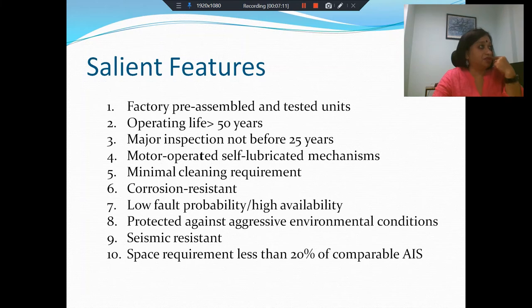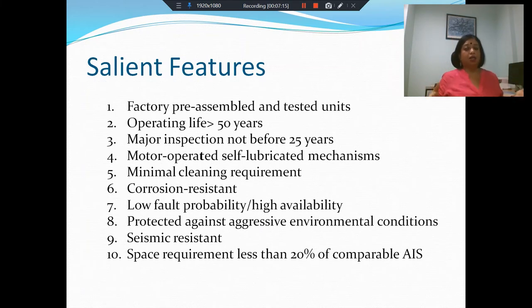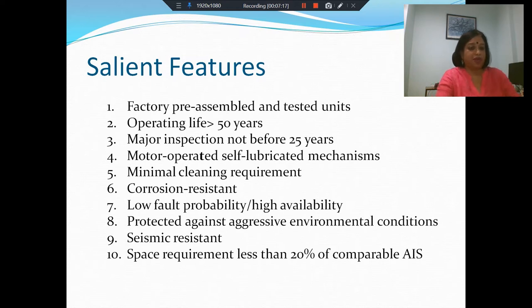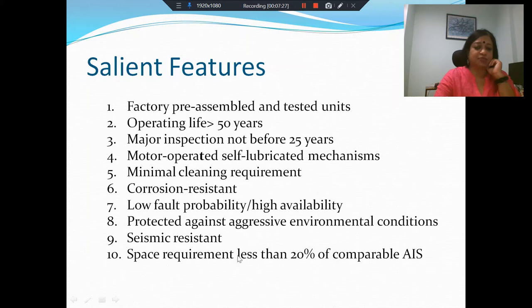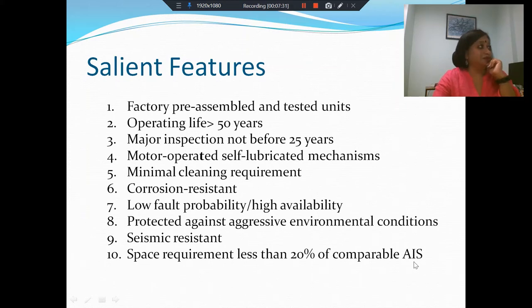When you have earthquakes, large extended open structures are vulnerable, but when you have something encapsulated and much more compact, it is less likely to be damaged. Most importantly, the space requirement is less than 20% of a comparable air insulated substation. This is very significant.